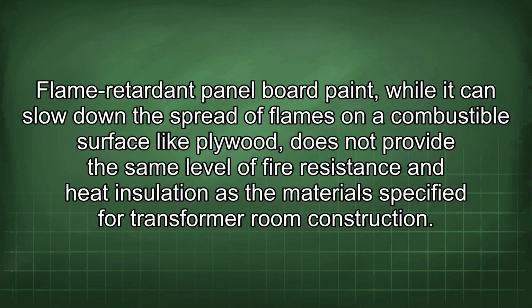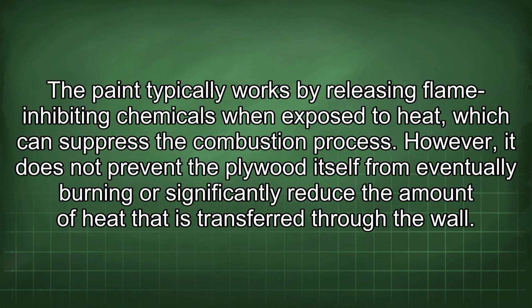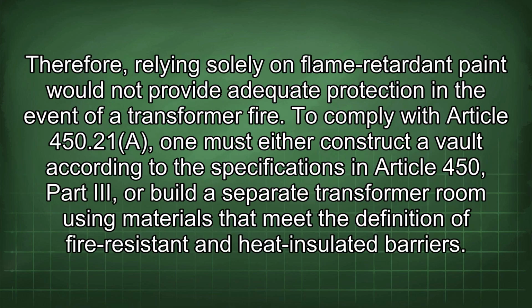Flame-retardant panel board paint, while it can slow down the spread of flames on a combustible surface like plywood, does not provide the same level of fire resistance and heat insulation as the materials specified for transformer room construction. The paint typically works by releasing flame-inhibiting chemicals when exposed to heat, which can suppress the combustion process. However, it does not prevent the plywood itself from eventually burning or significantly reduce the amount of heat that is transferred through the wall. Therefore, relying solely on flame-retardant paint would not provide adequate protection in the event of a transformer fire.